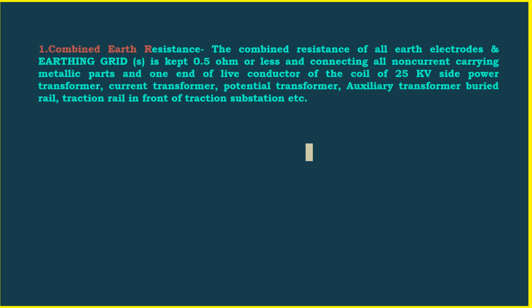The combined earth resistance of all earth electrodes and earthing mesh or grid is kept at 0.5 ohm or less, connecting all non-current carrying metallic parts and one end of the live conductor of the coil of the 25 kV side power transformer, current transformer, potential transformer, auxiliary transformer, buried rail, etc.